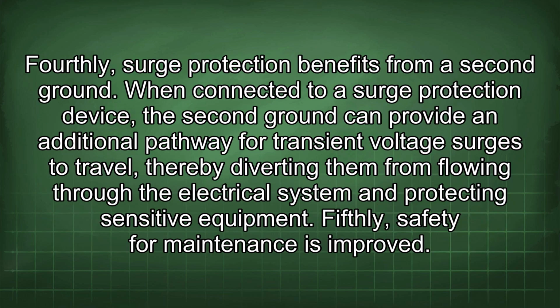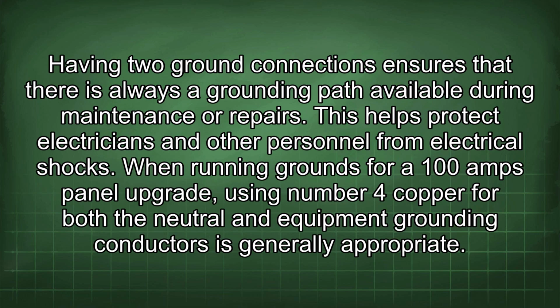Fourthly, surge protection benefits from a second ground. When connected to a surge protection device, the second ground can provide an additional pathway for transient voltage surges to travel, thereby diverting them from flowing through the electrical system and protecting sensitive equipment. Fifthly, safety for maintenance is improved. Having two ground connections ensures that there is always a grounding path available during maintenance or repairs. This helps protect electricians and other personnel from electrical shocks.